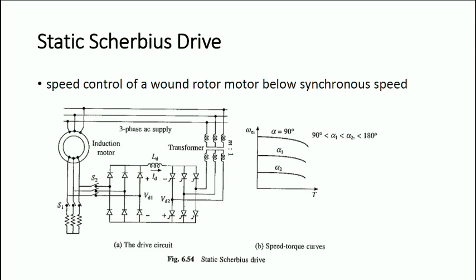Since active power is getting reduced and reactive power is getting increased, the overall power factor of the system will be reduced — the system runs at a reduced power factor. This is the basic principle of the static Scherbius drive. The torque-speed graph shows variation when alpha, the firing angle of the inverter, is changed. The firing angle varies between 90° and 180°, because for an inverter the firing angle must be greater than 90°. When alpha is 90°, you get the maximum speed.